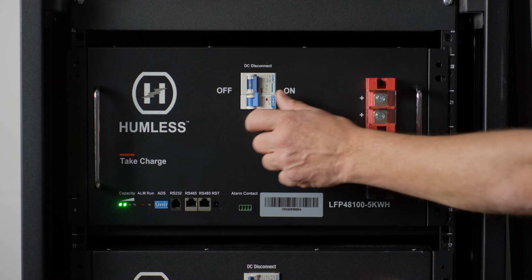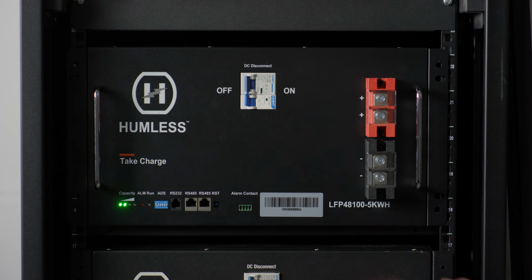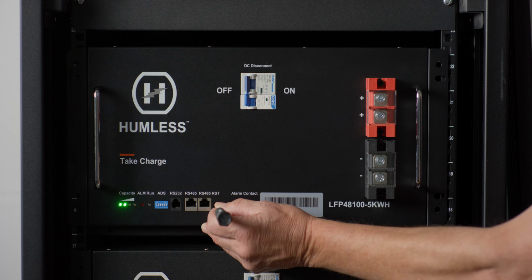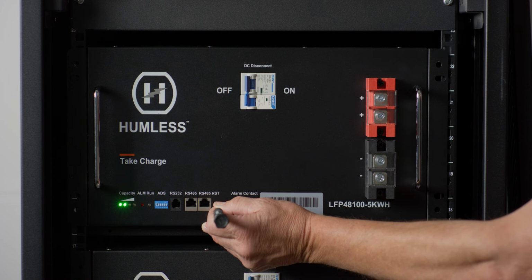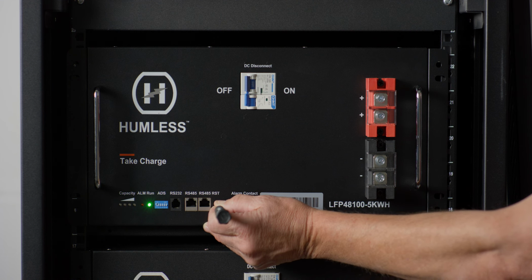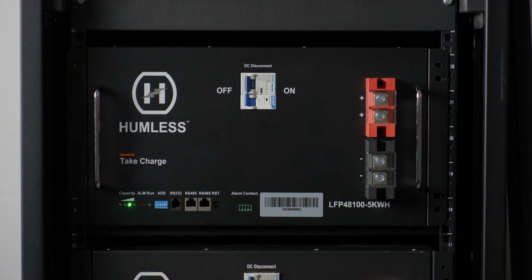If there is a need to shut down temporarily or for the season, this is a very simple procedure. Turn off the battery breaker first, then press and hold the RST button until the indicator lights flash. That long press takes about 5 to 6 seconds. Once the lights stop flashing, the battery is off and inert.